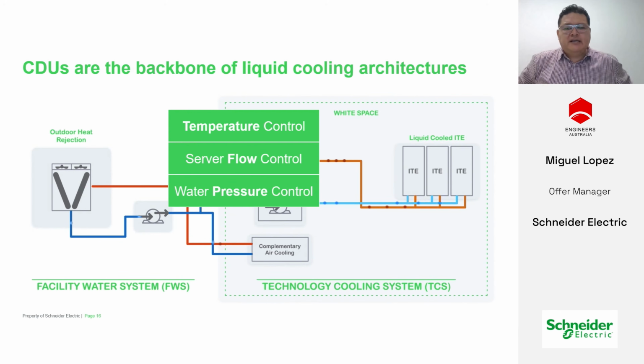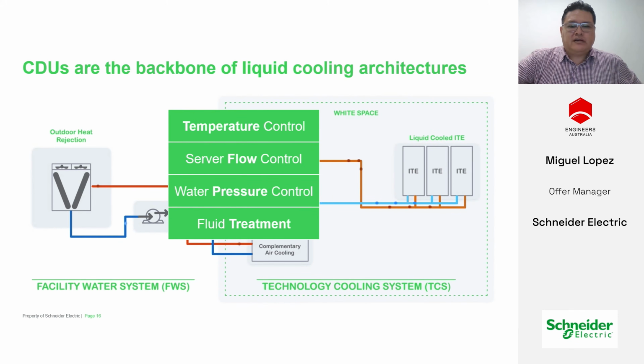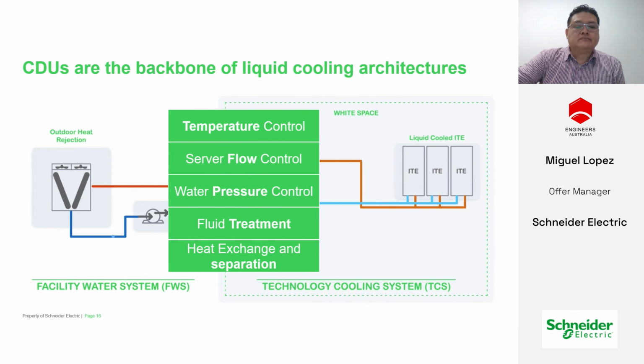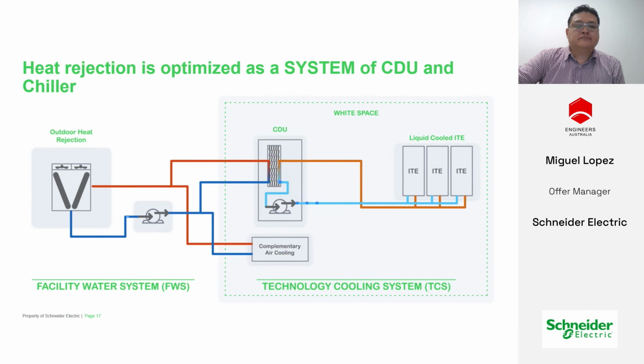When you have multiple racks, it could be quite challenging to make sure that each server in each rack is delivered with the appropriate water temperature, water flow, and that there's sufficient head pressure for the pump to be able to perform that duty. Fluid treatment over time, whether it's your TCS loop or your facility water loop, will require treatment. So there is a need to dose or treat the fluids. So the CDU is the point at which we will be doing the fluid treatment and where we do, obviously, the heat exchange between the technical loop and the facility water loop.